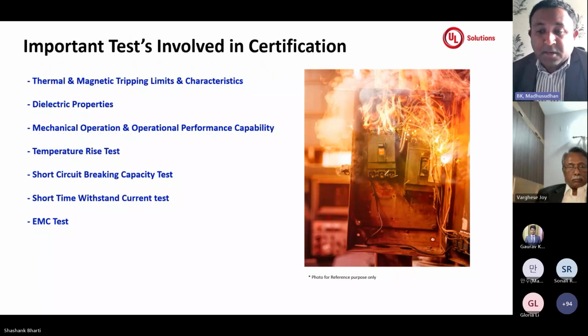Yeah, and coming back to the test, the major test that covers within the scope of 60947 Part 2 for breakers is thermal tripping limits and characteristics. Basically, this test is carried out on the breakers based on the declaration. It is nothing but an overload test on the products for thermal. Whatever the declaration from the customer, the reference temperature will be maintained for the particular breaker, and the breaker will be fed with the current on the settings that come from the standard, and the tripping time will be verified against the standard requirements.